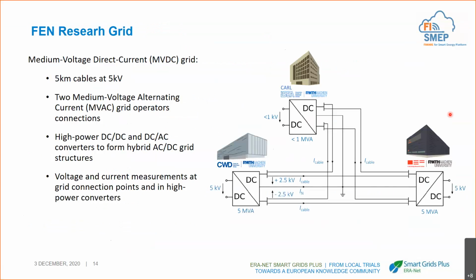Yeah, first of all, the monitoring of the medium voltage DC grid. As I said, we have a research grid in our campus, which has been built with a national project. And this is a scheme of the medium voltage part. In particular, we have 3 different buildings, which are interconnected by 5 kilometers of cables. The cables are at 5 kilovolt in DC. So each pole is plus minus 2.5 kilovolt.